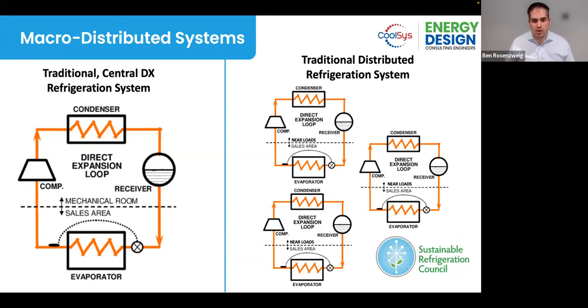So in a macro distributed refrigeration system, you'll have, like explained, multiple smaller systems that look like central refrigeration systems. However, the mechanical equipment, the compressor equipment, the receiver, that kind of rack package is located much closer to the individual loads that rack might be serving. The designer who puts that together can then more closely specify and design the specifics of that compressor system for the loads, the suction temperatures required, and the cases and coils that it's serving, thus reducing refrigerant charge, making other refrigerants potentially an option, as well as different design styles.